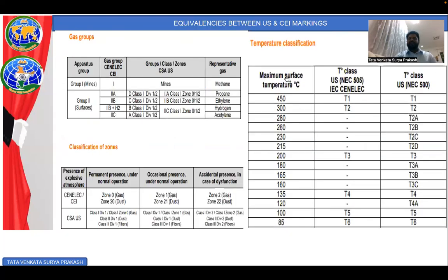So equivalencies between US and CE markings, we will just quickly go through it. For example, equipment or apparatus group 1 is for mines, so it is called gas group CE1, and group 2, if you say CSA US, it is called a mines group, and the representative gas is, for example, methane. And group 2 surfaces, for example, 2A, 2B, or 2B plus H2, and so on, is given there. So this is the D class at division 1/2, or class 2A with zone 0, 1 or 2. So like this it was given.